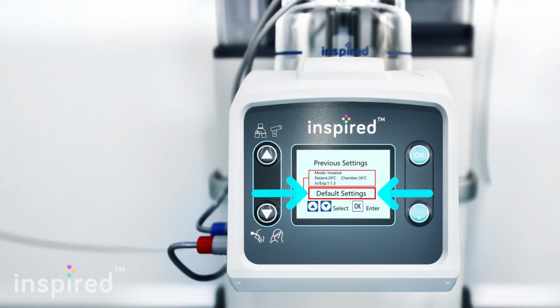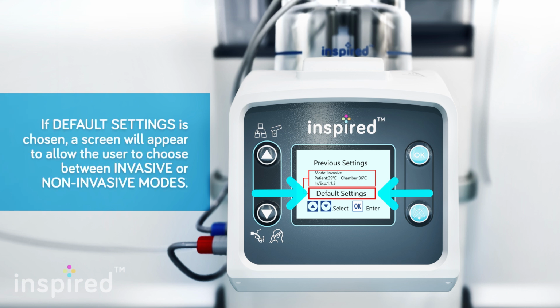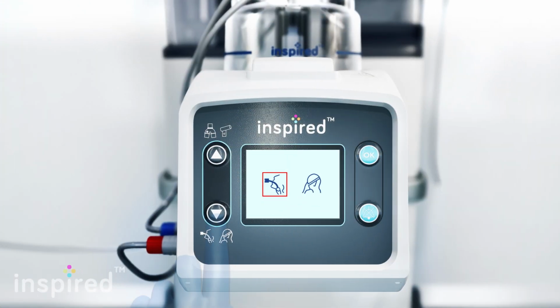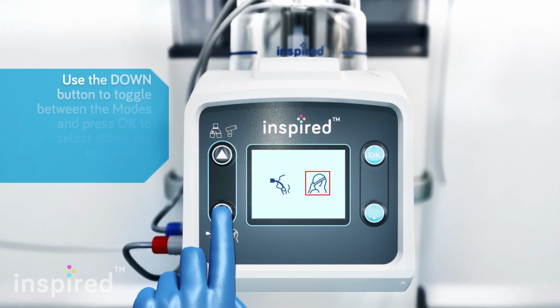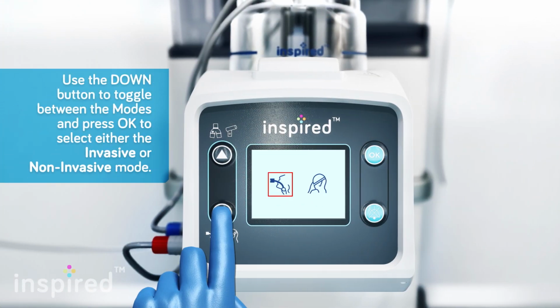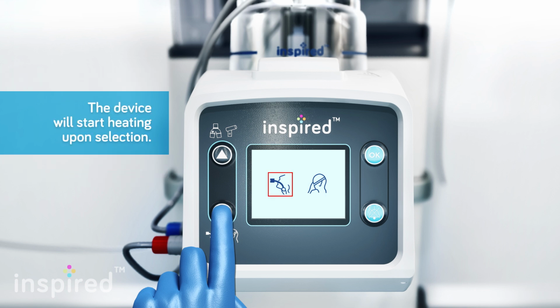If default settings is chosen, a screen will appear to allow the user to choose between invasive or non-invasive modes. Use the down button to toggle between the modes and press OK to select either the invasive or non-invasive mode. The device will start heating upon selection.